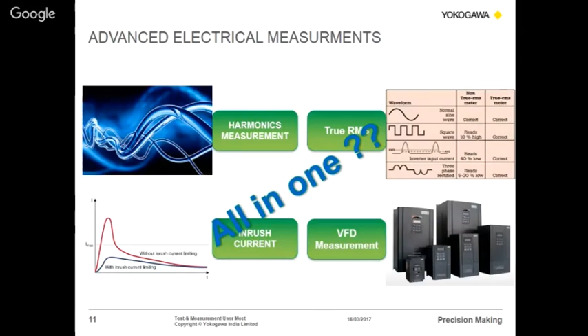VFD measurement normally depends on the load, as the frequency modulation changes depending on the load. For a variable frequency drive, pulse width modulated waveforms are incorporated in the drive system, and depending on the load, the pulse width is modulated and the respective power is transmitted to the load. All in one, it is possible.